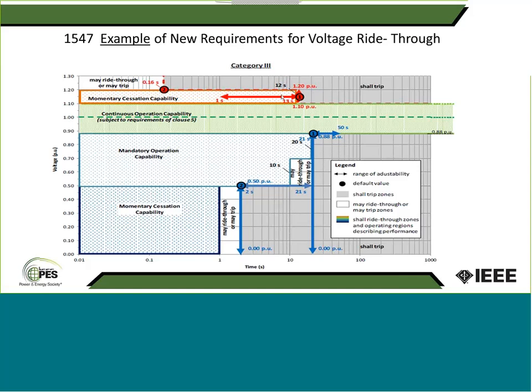So let's start with the two blue points, 1 and 2, and the red. These are the default values for trip. For blue, for example, number 2 here is 50% trip at 2 seconds. That's the default. The arrows show the ranges of adjustability. Some of the requirements for ride-through in some parts of the country may be a bit different than in other parts, due to penetration of renewables, and some countries that are adopting 1547 may not be happy with those default numbers. So the arrows are there so that the engineers can request a different setting for trip.